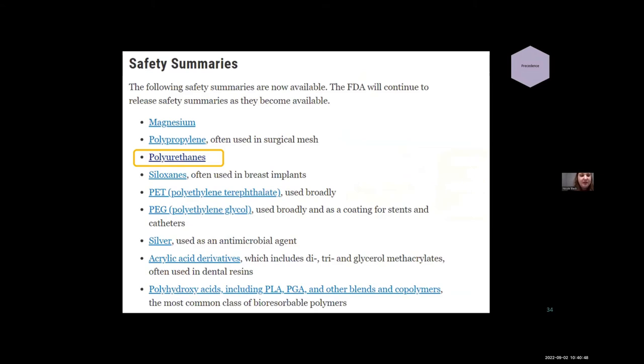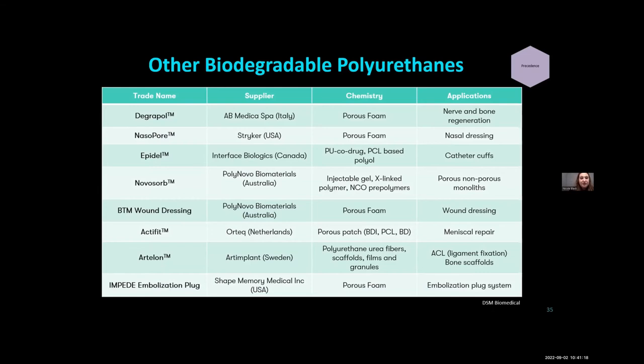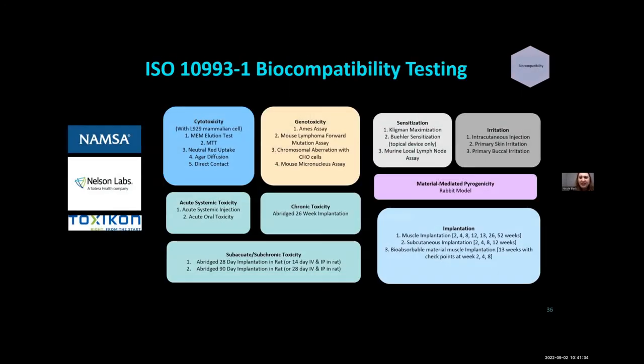Precedent is another thing I talked about. You want to ensure the material systems you're using have precedent in other medical devices. Polyurethanes are a class of materials that have safety summaries published by the FDA. If you're considering using a new material in a medical device, sometimes the FDA will already have guidance around how it can be used and how much can be present. We also wanted to make sure there was precedent for using these polyurethanes in other medical devices. There's a wide variety of medical devices, in the US, Europe, Canada, and Australia, that use different biodegradable polyurethanes.